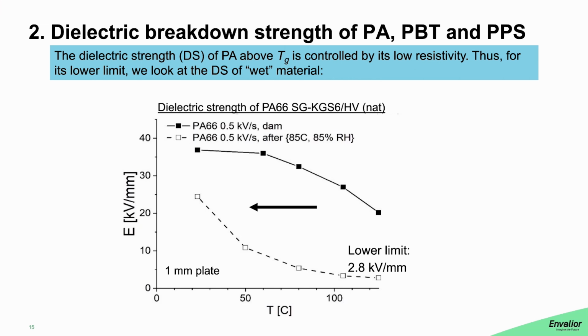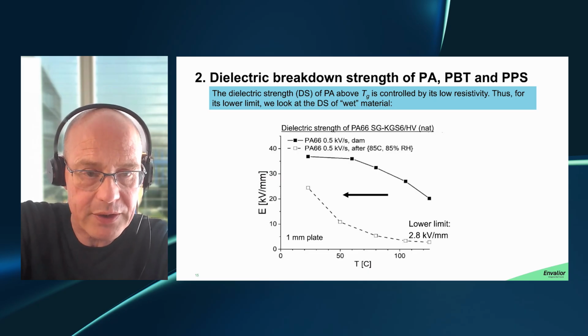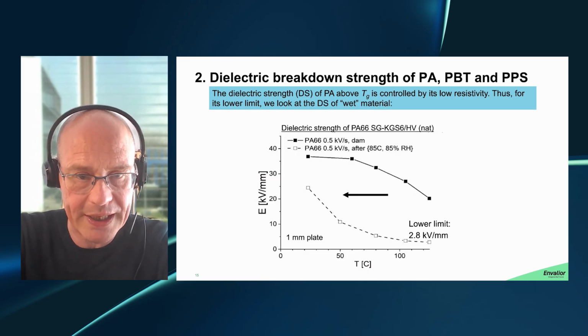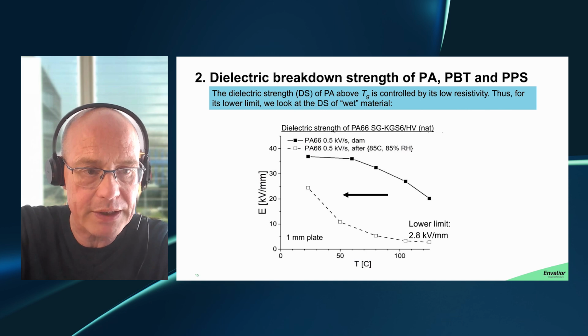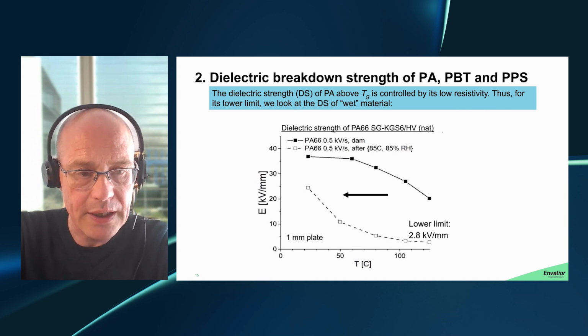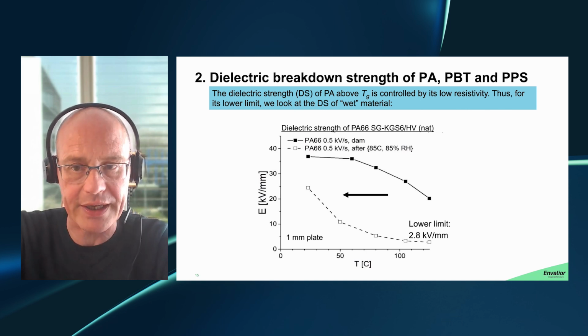And what you see is if you have conditioned your material at 85% relative humidity, so now it's in the fully wetted state, then at high enough temperatures, your breakdown field moves to 2.8 kilovolts per millimeter. So that is basically the lowest strength you can encounter for a polyamide, and that is the type of value you can use in your high voltage engineering applications.